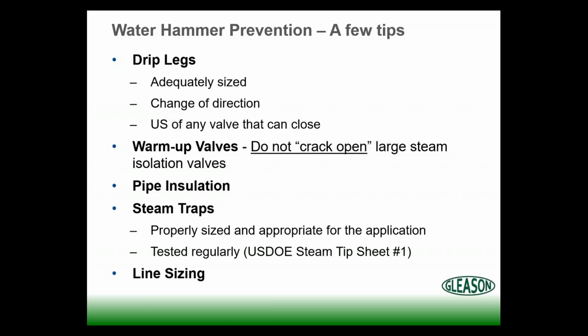Pipe insulation. If your folks are doing any work on your system and they pulled off the insulation, please put it back on before you crank up, because many times, with less insulation or with no insulation, we're going to generate more condensate. It can easily overwhelm our steam traps. It may not have been sized for that load. And of course, steam traps, we want to make sure we properly size them, make sure they're appropriate, and please test them regularly.